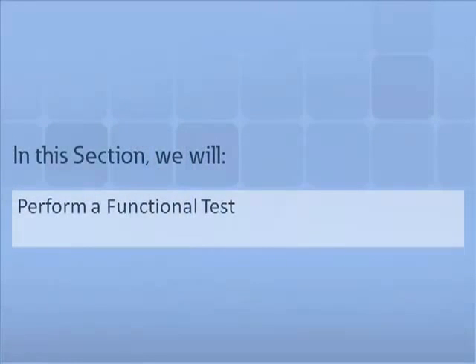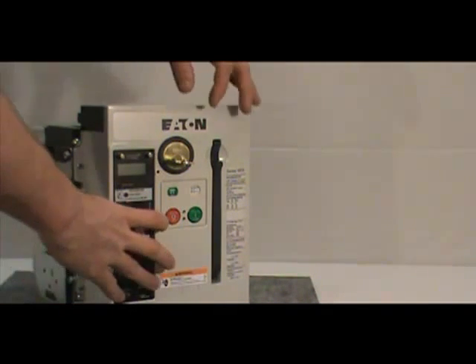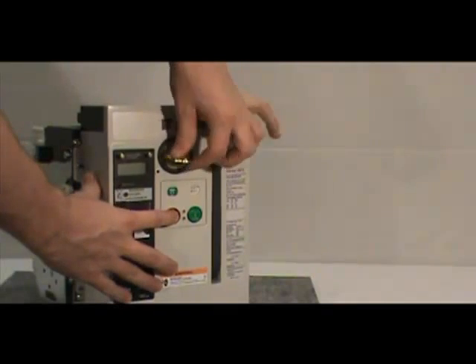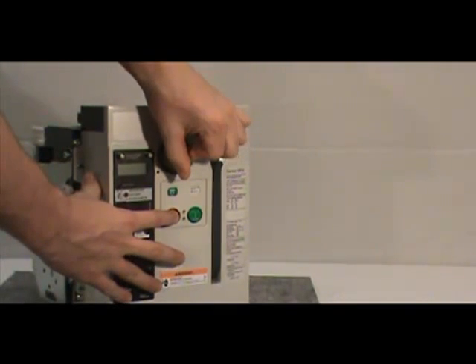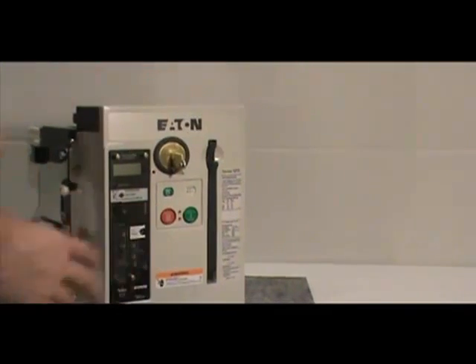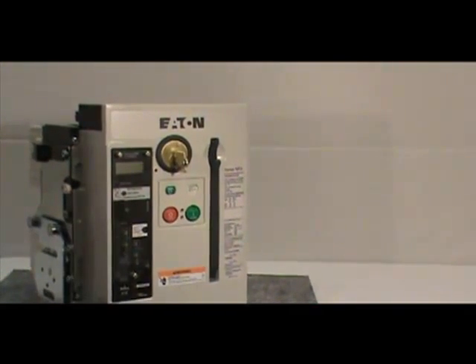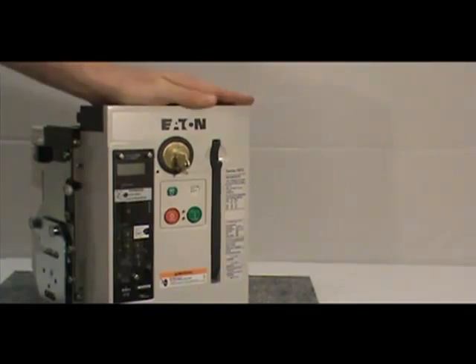In this section, we will perform a functional test. To begin, press the red button down while rotating the key counterclockwise. Next, remove the key and charge the breaker.